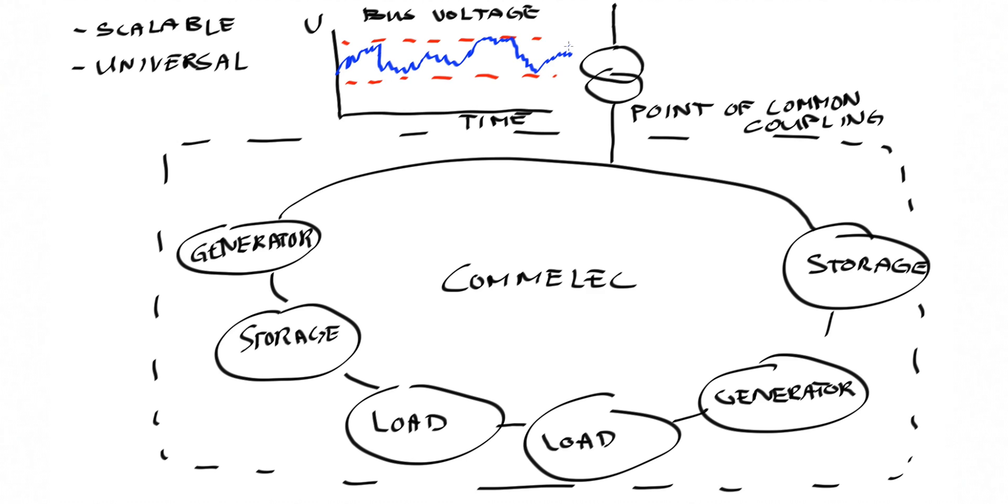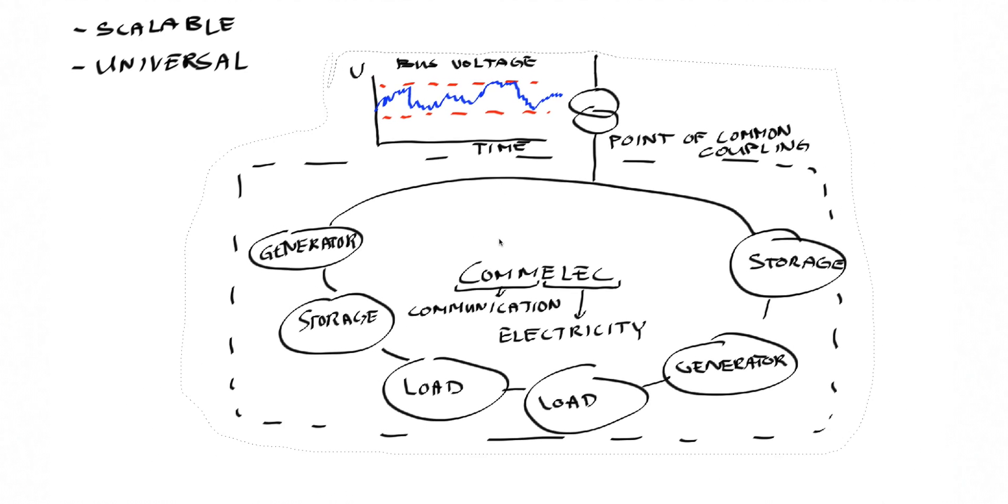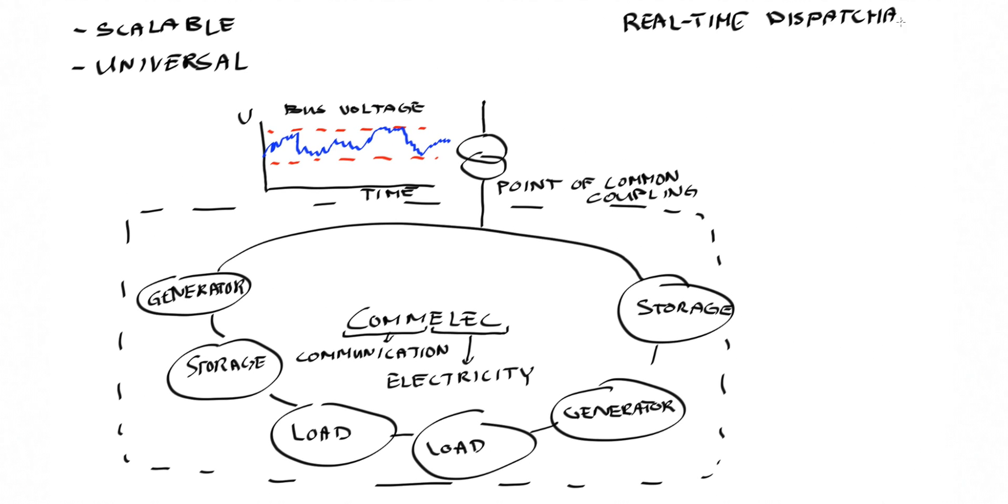Hence, voltage and line current violations are avoided by construction. The framework has several benefits. COMMELEC computes optimal control decisions, where the optimization criterion can be influenced by individual resources. It can accurately track a target power profile at the point of common coupling of the grid, which means that a COMMELEC-controlled subgrid can operate as a virtual power plant and can be used instead of conventional fuel-based generators to maintain power balance.